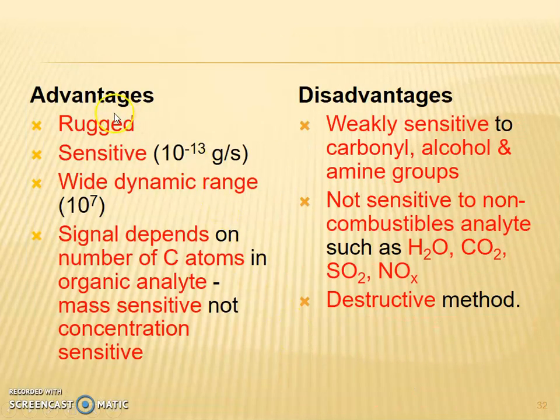The advantages: rugged, sensitive, wide dynamic range. The signal depends on the number of carbon atoms in the organic analyte. It is mass sensitive, not concentration sensitive. However, the disadvantages are that it is weakly sensitive to carbonyl, alcohol, and amine groups, and not sensitive to non-combustible analytes such as water, CO2, SO2, and NOx, and it is thus a destructive method.